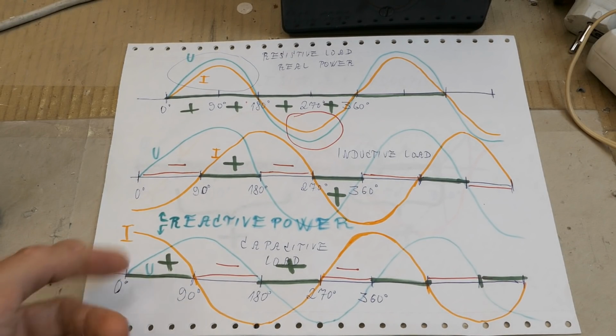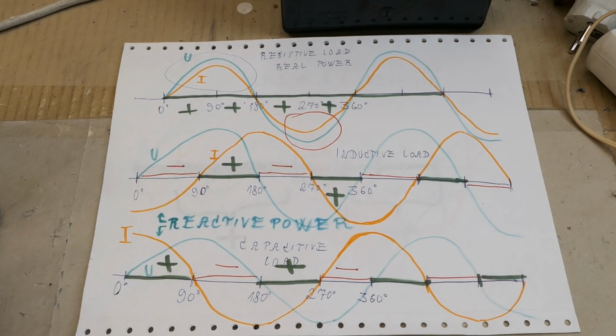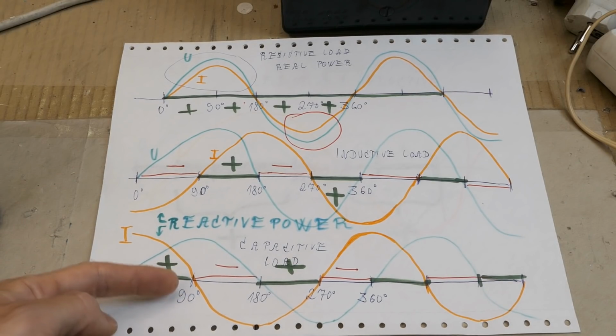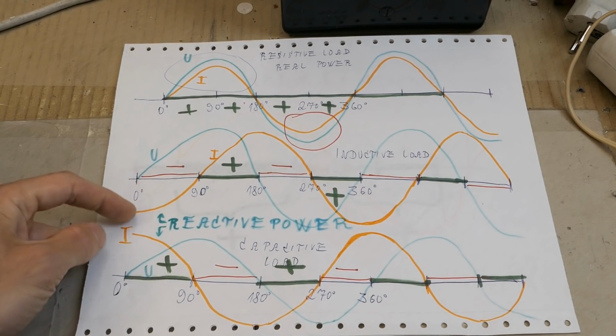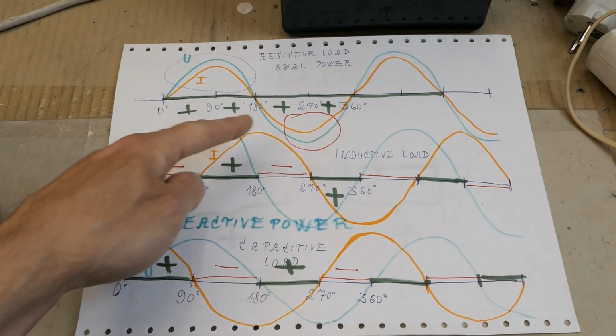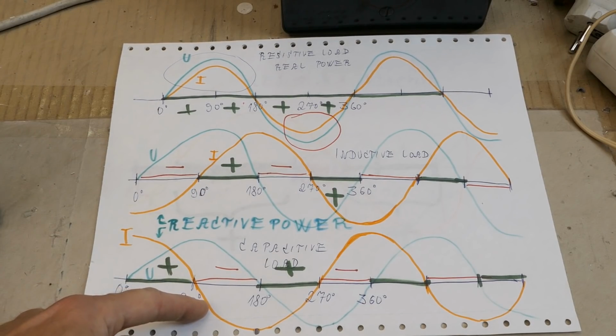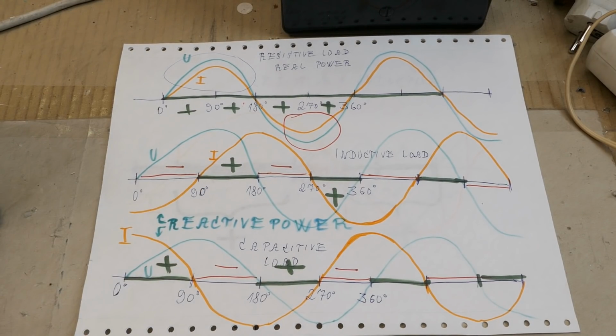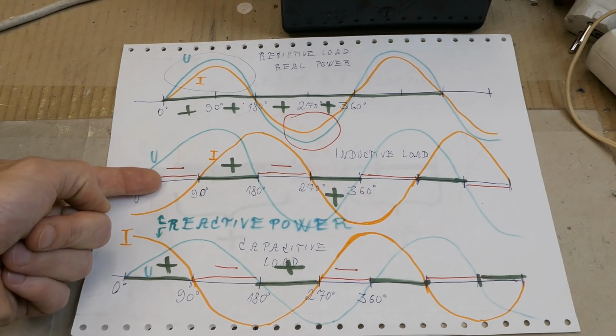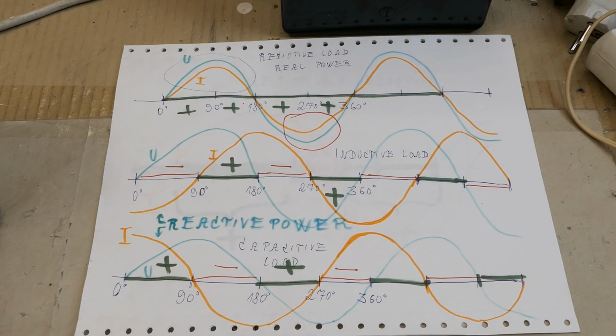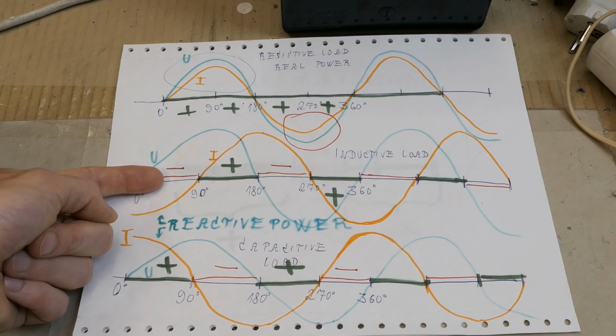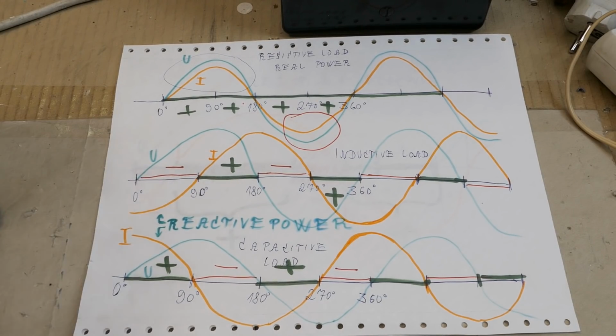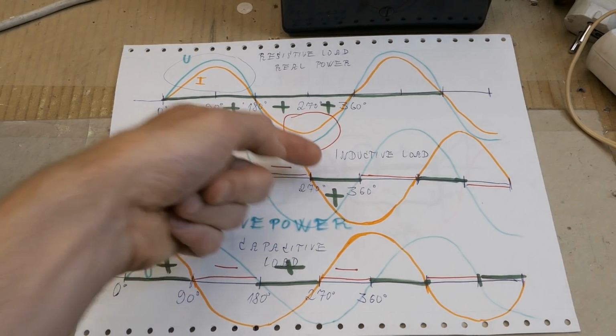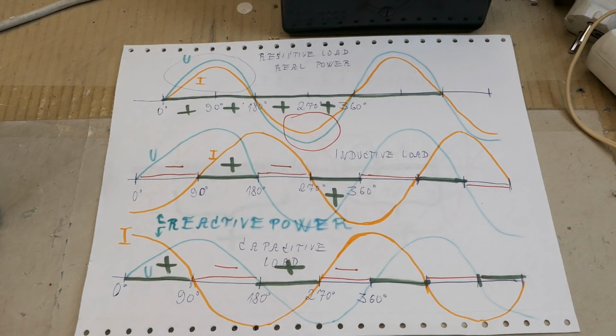The power goes one way and then the other way, and it alternates. But they can compensate each other. Inductive can compensate capacitive, and capacitive can compensate inductive. Because as you can see, the current goes the opposite way. An inductive current and a capacitive current are rotated 180 degrees. So for example, an inductive load can be compensated using a capacitor, and then it doesn't have to pull the reactive power through the long power lines and exchange it with the power plant. Instead of it, it's just exchanging it with the capacitor, which is much closer to it, and so it doesn't cause an unnecessary load on the power lines.